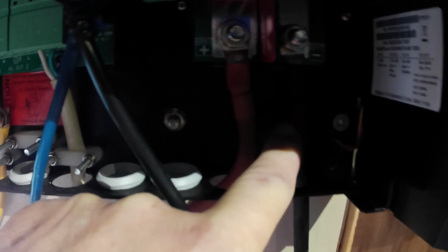A few weeks ago, I was sitting at my desk and kept hearing this buzzing sound, the lights were flickering, the UPSs were going off, all kinds of weird stuff. I came over here and finally isolated it to that positive connection — I hadn't tightened down that bolt properly. So double check your work. It ran fine for days with no indication of a problem; I thought the damage to the inverter had finally caught up with me, but it was just a simple mistake of forgetting to tighten that cable.